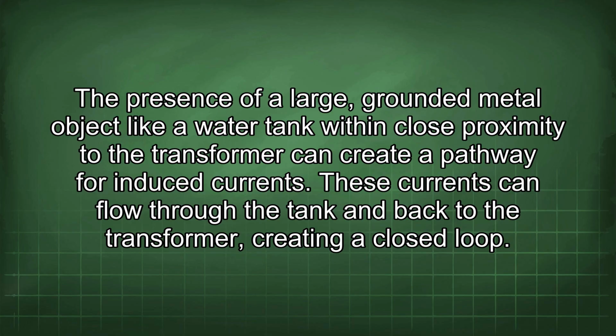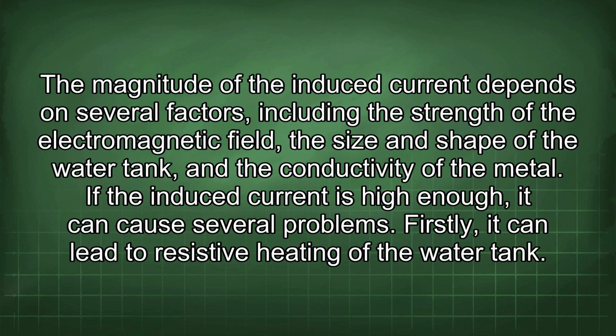The presence of a large, grounded metal object like a water tank within close proximity to the transformer can create a pathway for induced currents. These currents can flow through the tank and back to the transformer, creating a closed loop. The magnitude of the induced current depends on several factors, including the strength of the electromagnetic field, the size and shape of the water tank, and the conductivity of the metal.